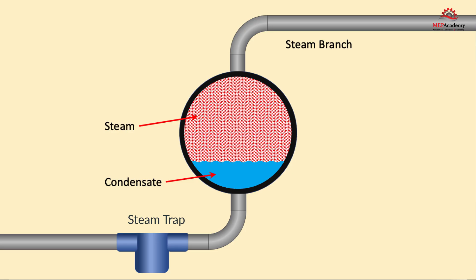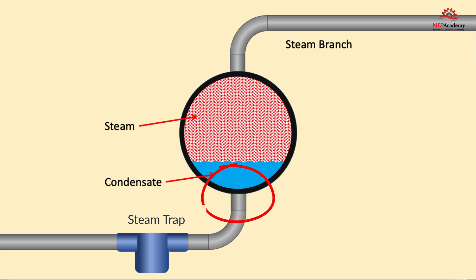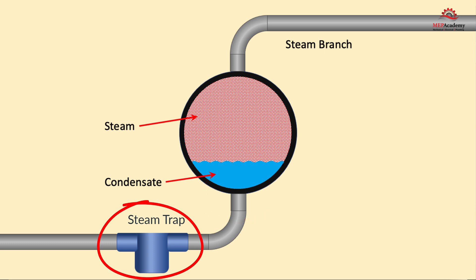It's important that any steam branch line be taken off the top of the main steam pipe in order to prevent pulling condensate into the branch. As you can see, steam will rise to the top because of its lighter density and higher temperature. For similar reasons, you want to make any condensate branch connections off the bottom of any steam line or system to ensure that you are only pulling condensate, and all condensate branches should contain some type of steam trap to ensure that only condensate passes through to the condensate system.